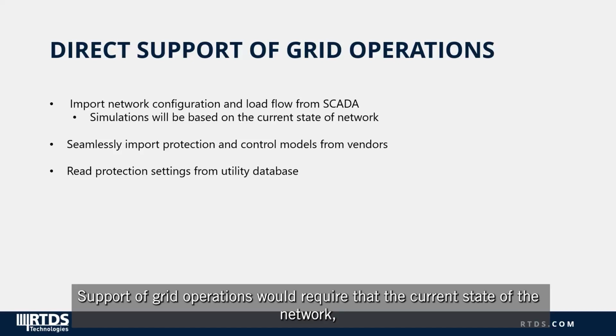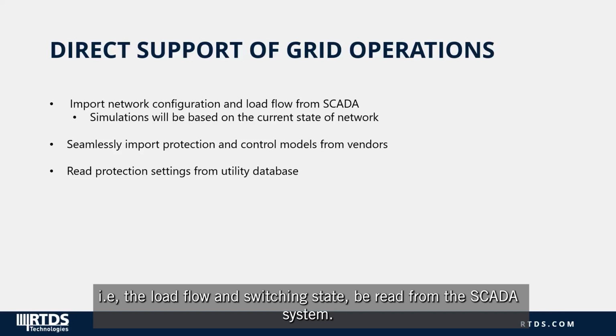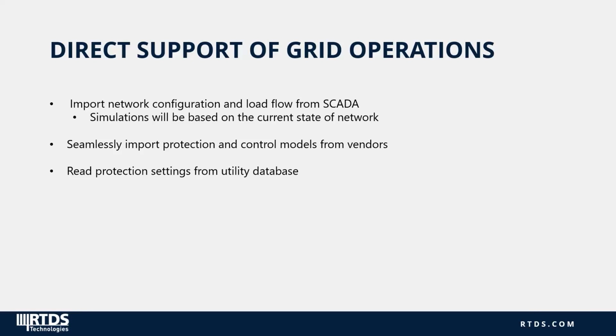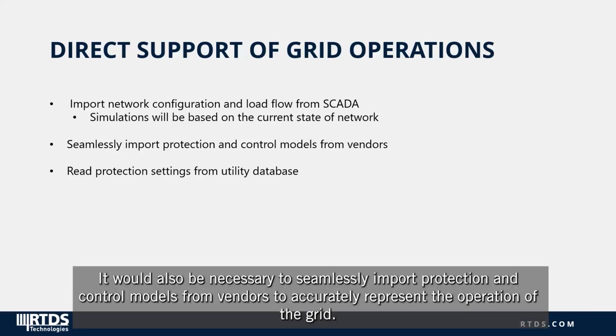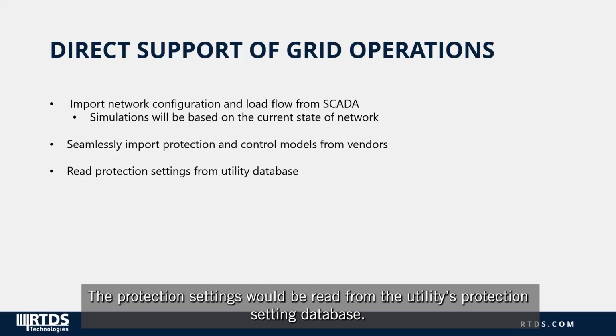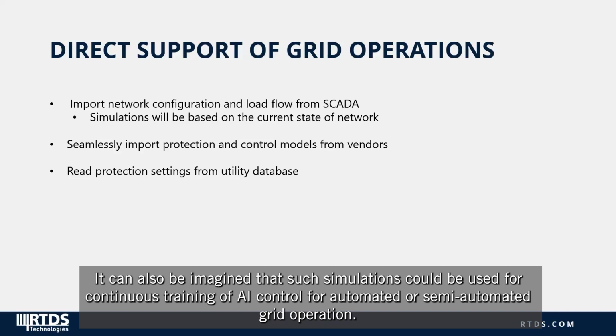Support of grid operations would require that the current state of the network, i.e. the load flow and switching state, be read from the SCADA system. It would also be necessary to seamlessly import protection and control models from vendors to accurately represent the operation of the grid. Protection settings would be read from the utility's protection settings database. It can also be imagined that such simulations could be used for continuous training of AI control for automated or semi-automated grid operation.